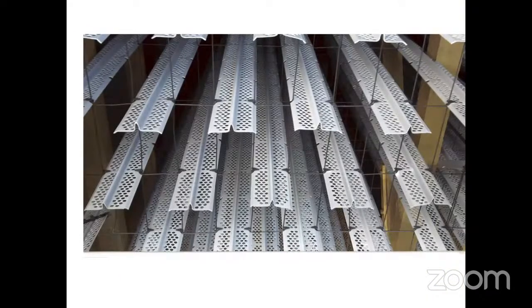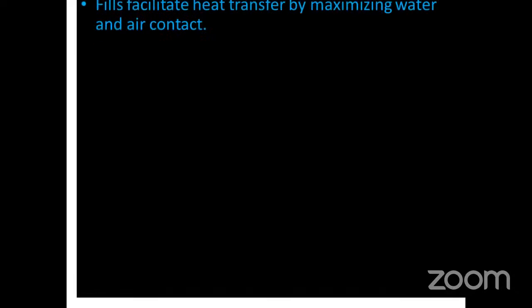Yes, sir. You can see the fills, sir. Water is made to fall on the top. These fills separate the water, making it into fine particles, so that the water gets more contact area with the upcoming air. Fills facilitate heat transfer by maximizing water and air contact. Fills can be splash type or film type. Splash means it makes particles. Film means it makes a continuous film. In both cases, the contact area is increased.